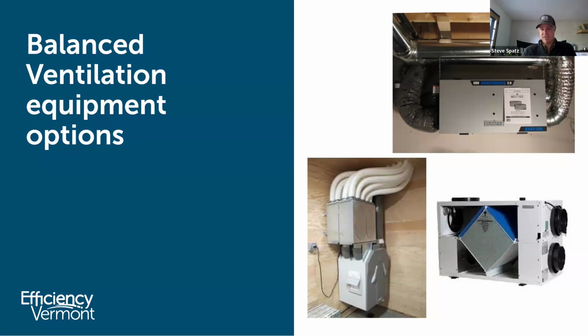A lot of different options of equipment on the market. Most systems are intended to be connected with site-built duct systems and rigid ductwork and/or flexible ductwork off the unit itself and move throughout the building. There are some manufacturers, Zehnder specifically, which is a European manufacturer that has a manifold and home run system essentially from their units, where you have small diameter flexible duct that goes throughout the building to each individual room, and each of those ducts comes back directly to a manifold from the piece of equipment itself.